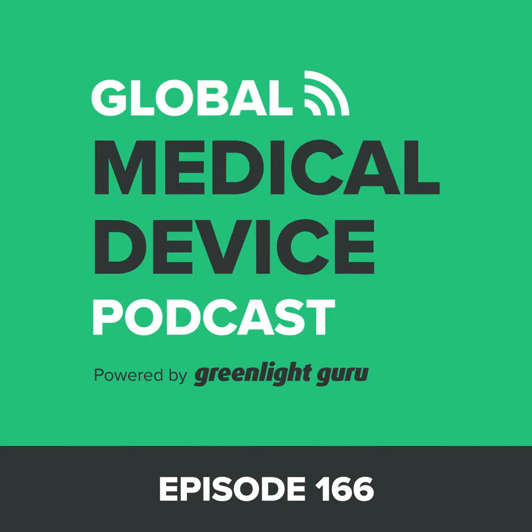If there's a section that's blank or omitted, FDA has no idea why that section is not there. Is it not there because it's not applicable, or is it not there because you just simply forgot about it or didn't know about it? So even in a case where biocompatibility for software, that would be kind of a stupid thing for somebody to talk about, you say in there, not applicable.